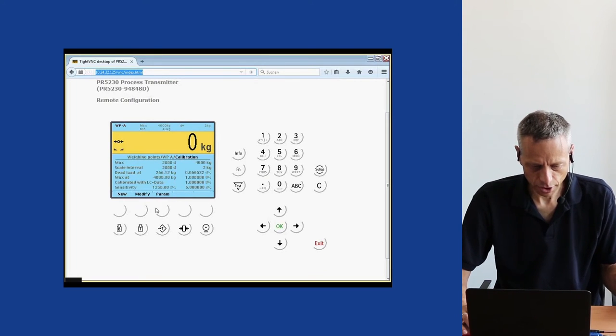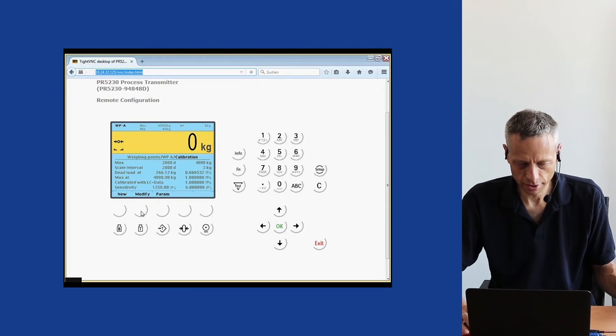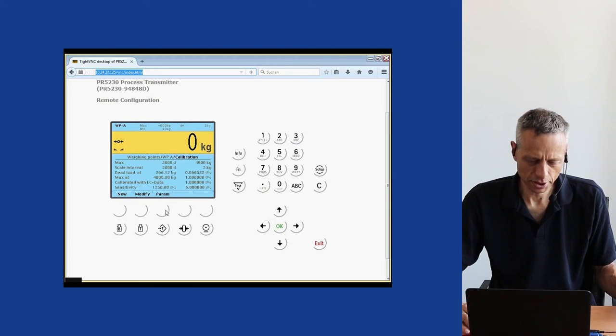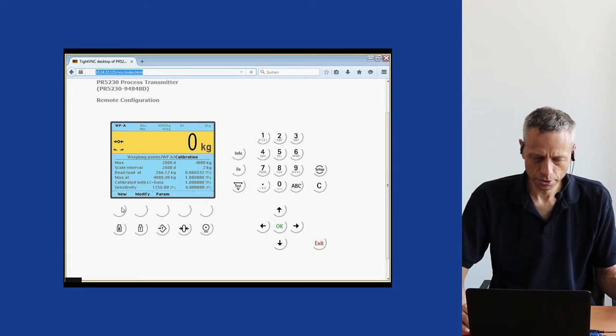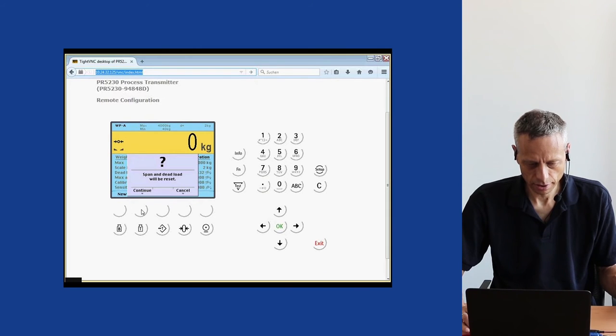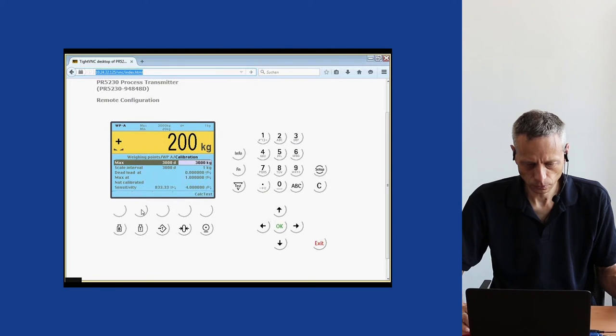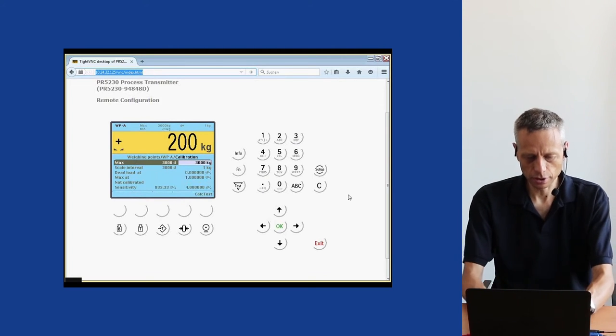We have three choices: new calibration, modify an existing one, and change parameters of the weighing point. Parameters are not related to the calibration directly. We enter a new calibration and accept that the span and dead load of the former calibration will be reset. The first step is to enter the new max load, which we set to 3000 kg.